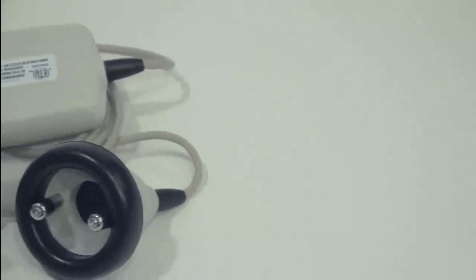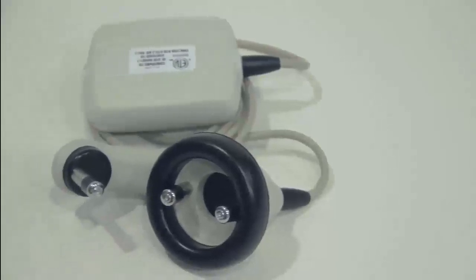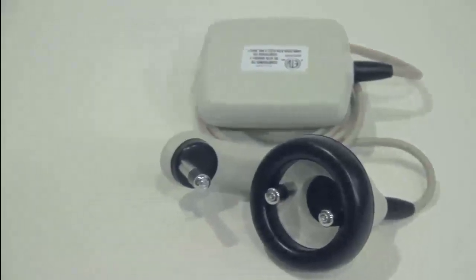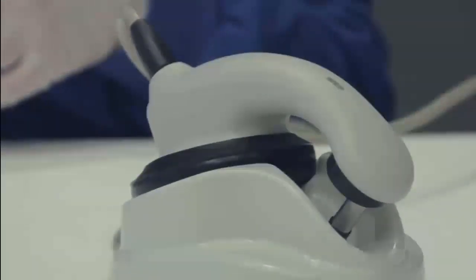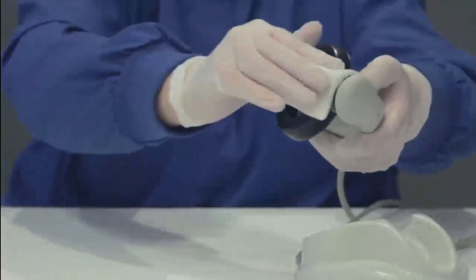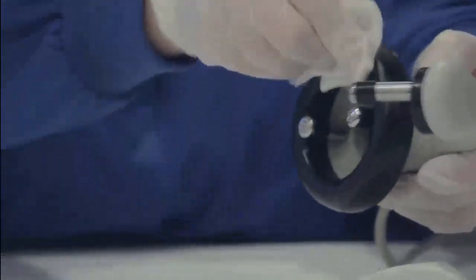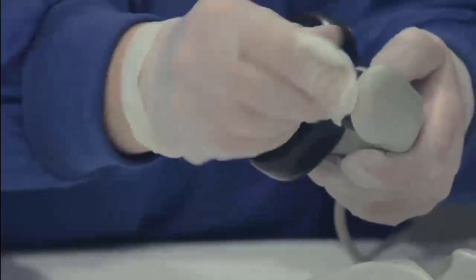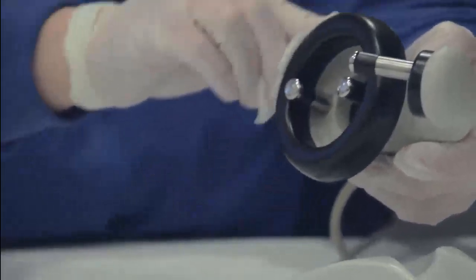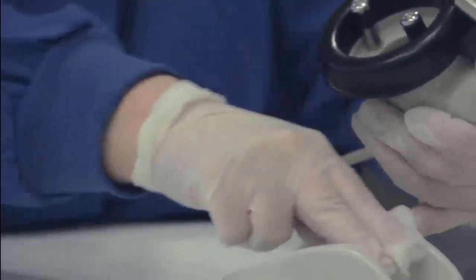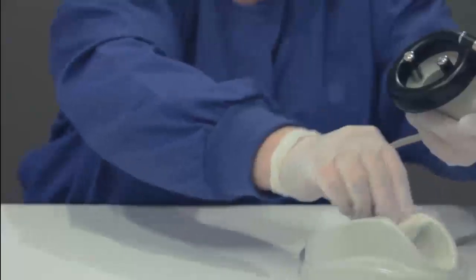The BERAphone is intended for use on intact external skin around the ears and on the scalp. It should not be used if the skin has any open wounds or sores, or if the baby has a contagious skin condition. The BERAphone must be cleaned and disinfected after use on each baby. Clean off any residual gel from the electrodes and ear cushion using a gauze pad or disinfectant wipe. If you set the BERAphone in the cradle during the baby's screening, it must also be cleaned and disinfected.